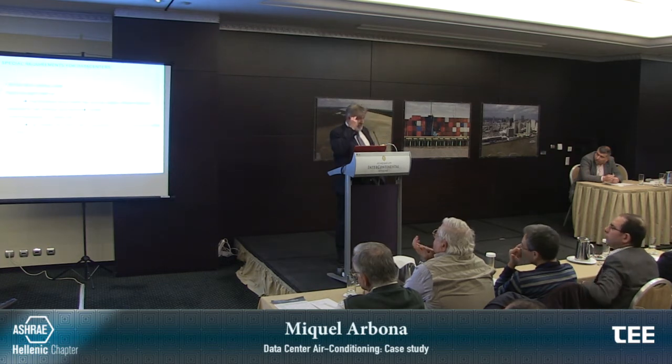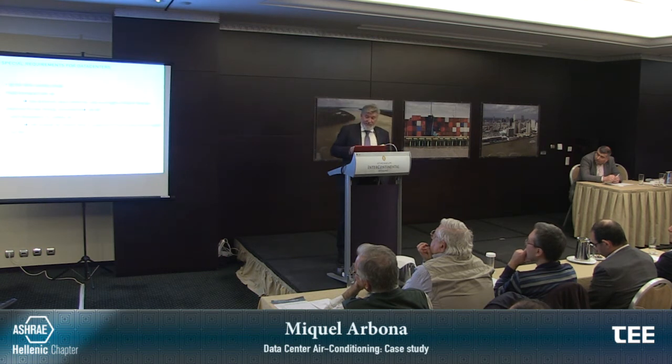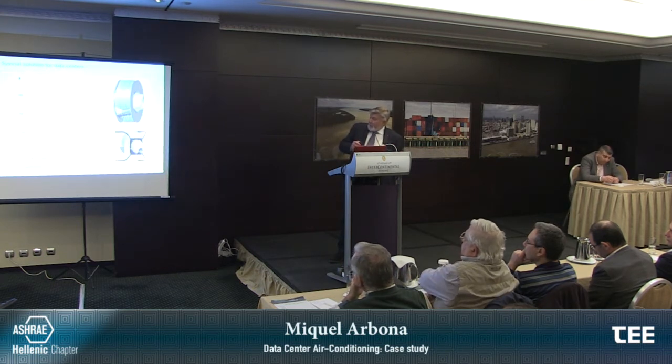But it is a special case of a data center. When you talk about a data center, you are not talking about ventilation some hours a day. It's 24 hours, 365 days per year. So the pressure drops are very important. Even a little pressure drop in the circuit means bigger consumption. So the thing is to reduce the pressure drop. So a new unit has to be designed, thinking about limiting all the pressure drops in the circuit of the adiabatic system and heat exchanger. And then what else you can do is put in better fans.